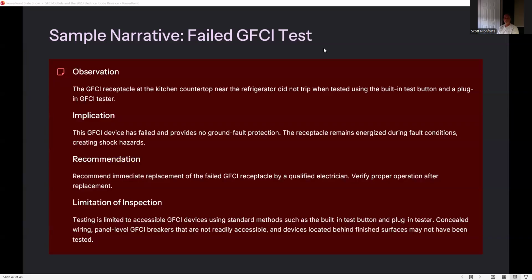Observation: the GFCI receptacle on the kitchen countertop near the refrigerator did not trip when tested using a built-in test button and plug-in GFCI tester. Implication: this GFCI device has failed and provides no ground fault protection. The receptacle remains energized during fault, creating shock hazards. Recommendation: recommend immediate replacement of the failed GFCI receptacle by a qualified electrician. Verify proper operation after replacement.